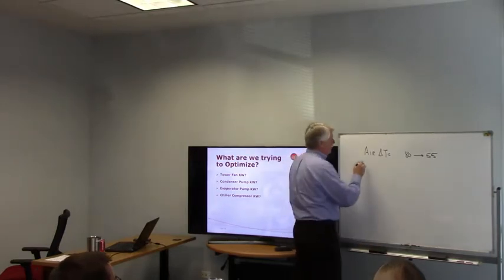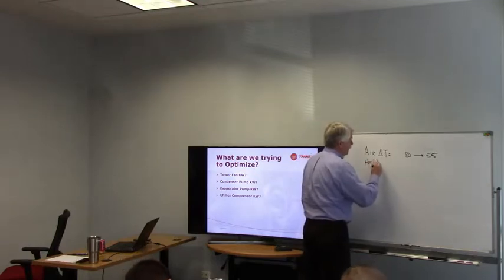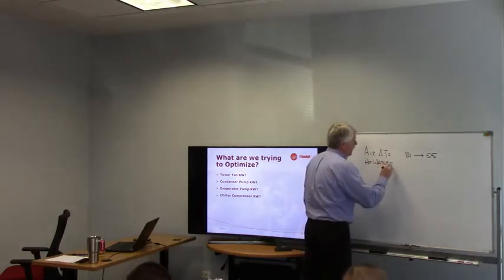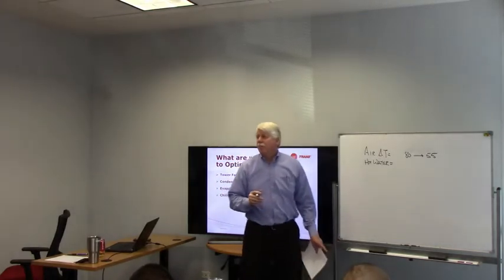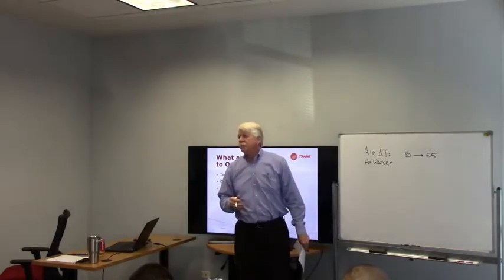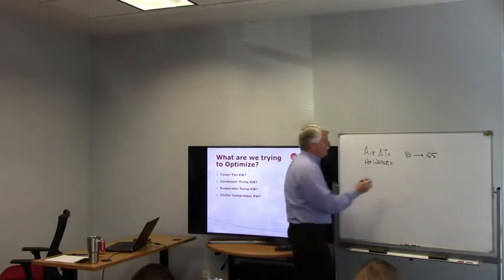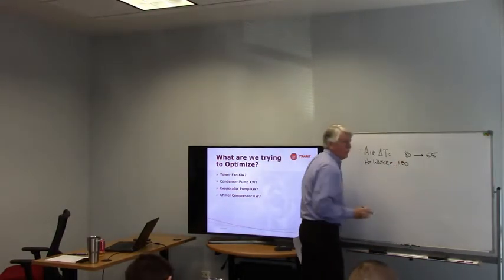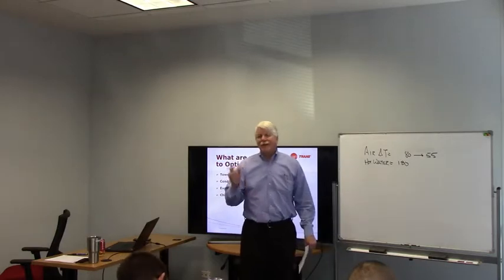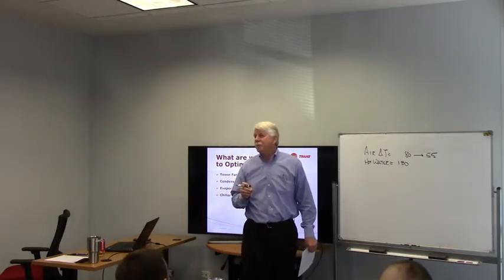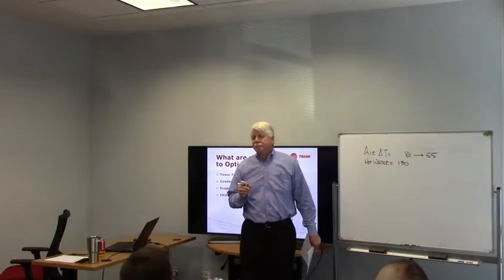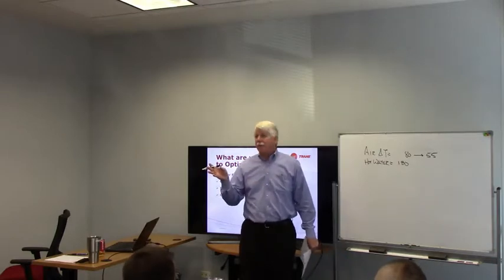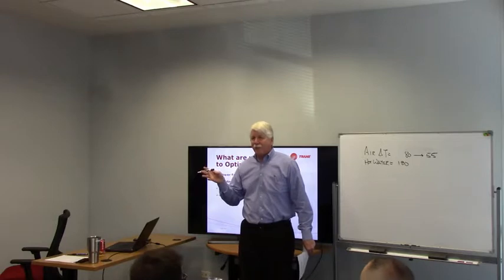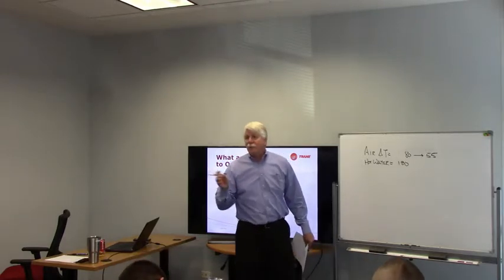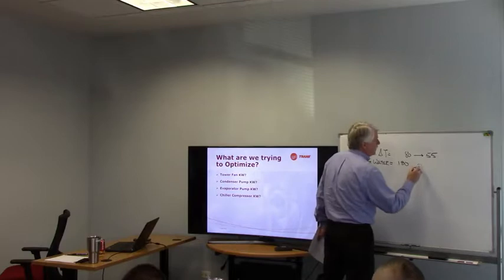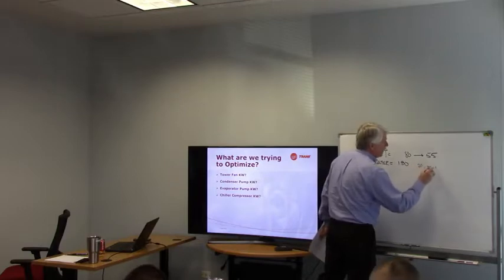Let's see, hot water. What are most systems designed at for supply hot water temperature? 120 to 180. Okay, 180 is usually the design, pretty much. Does anybody know what kind of delta T's they're designed on? 30 degrees. 20. 30 to 40. Do I hear any other votes? First of all, everybody's right. There's really 3 different designs you'll see. One is a 20, one is a 30, and one is a 40.